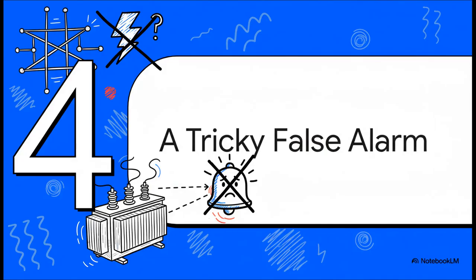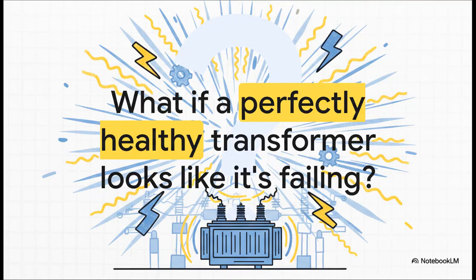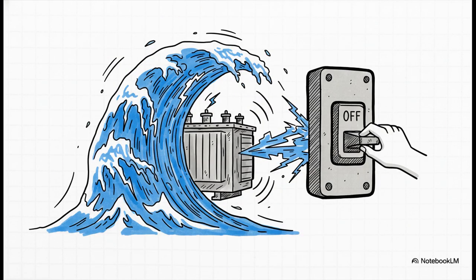But this is where the story gets even more clever. The grid's immune system is so sensitive that sometimes a perfectly healthy organ can look like it's in deep trouble. So this creates a real challenge. How do you avoid a false alarm? Just think about it for a second. What happens when you turn on any huge piece of equipment? It doesn't just quietly hum to life. There's this initial jolt of energy it needs just to get going. Well, this exact thing happens with transformers. It's called magnetizing inrush current.